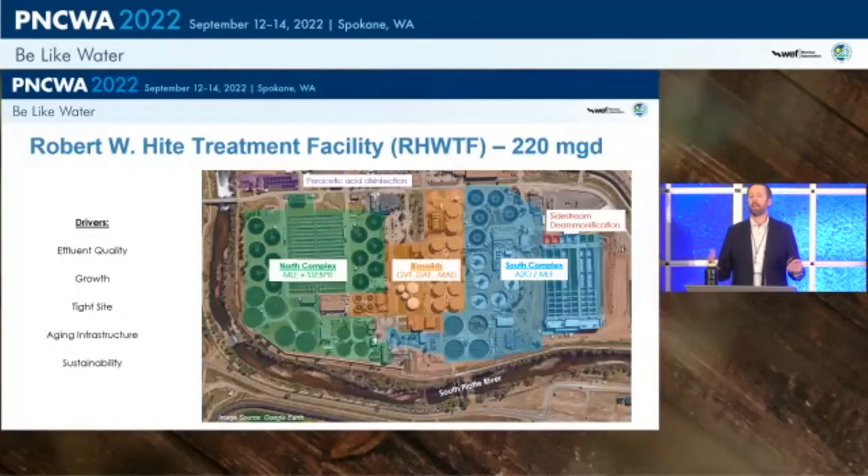Starting with the background, it's important to understand the Hite facility. This is a photograph of the Robert W. Hite facility — a 220 MGD rated facility located in the heart of Denver. The plant is divided into two equal-size capacity trains: a north secondary process with an MLE configuration and a side stream BIO-P configuration, and a south complex with an A2O facility with the flexibility to run as an MLE. Biosolids is in the middle with gravity thickeners for primary sludge thickening, DAF, mesophilic anaerobic digestion — two-phase, acid phase and gas phase — plus side stream deammonification. They also disinfect with peracetic acid.